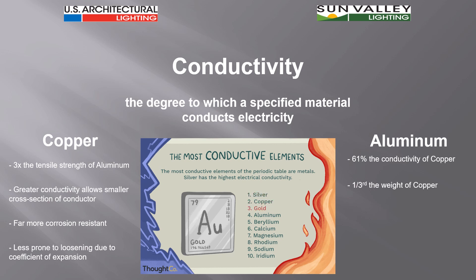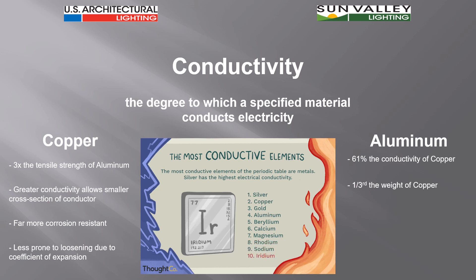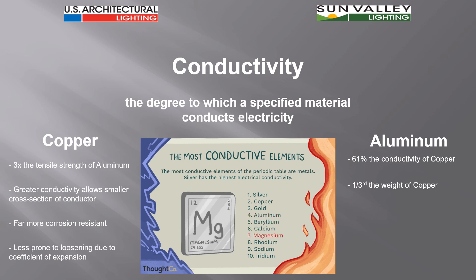Aluminum in its raw state has only 61% the conductivity of copper, but it's also only one-third the weight. So though it's less conductive when comparing the same wire sizes, aluminum is much lighter. Even if you used a cross-section twice the size of copper, it would still weigh less. As a result, we see aluminum wire used in high-power transmission lines because you can run great distances, carry the necessary electricity without tremendous losses by increasing conductor size, and the weight of aluminum plays in its favor.